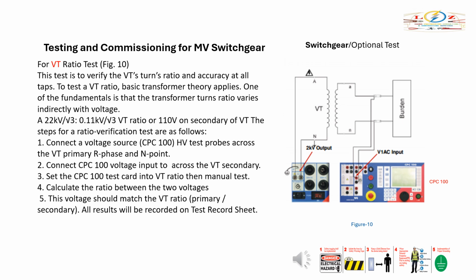The steps for a ratio verification test are as follows. 1. Connect a voltage source, CPC 100, HV test probes across the VT primary R phase and N-point. 2. Connect CPC 100 voltage input across the VT secondary. 3. Set the CPC 100 test card to VT ratio, then manual test. 4. Calculate the ratio between the two voltages. 5. This voltage should match the VT ratio, primary to secondary. All results will be recorded on test record sheet.